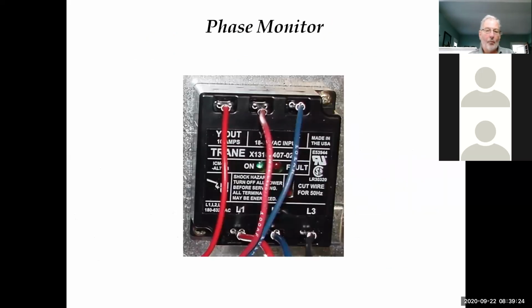All right, we do have phase monitors on all of our three-phase equipment, so don't get caught on that one. Basically what you have is a Y in and a common and a Y out. So this feeds the phase monitor and this feeds the system. That lets the power go through, feeds the system. And you should have either a green light or a red light. I have seen them with the green light on and the phase monitor is still not working, so don't trust that. Go here and take a voltage reading.